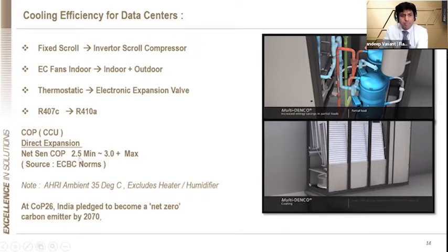As per the ECBC norms, specifically for the PAC units which sit in the data center, the COP should be 2.5 to a max of 3 or above. Higher is better. What is COP? 3.516 divided by IKW per ton. IKW is the kW power consumption of the compressor, what we saw here. So the higher the COP, basically the better, and thereby the PUE would also reduce. Also, India took a pledge at COP26 that we go net zero carbon emitter. So I'm sure all of us should drive towards this and take the pledge towards net zero carbon emission.